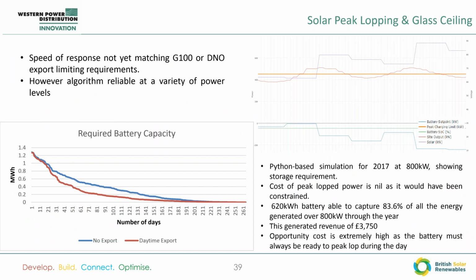So this graph shows how much energy storage would have been needed to peak lop at 80% of the overall power in 2017. Selected 80% because 20% oversizing was deemed to be the smallest oversizing a developer would have the extra expense of looking at a battery rather than just software limiting inverters, because quite a lot of solar parks just have a very high DC to AC ratio and they don't have any batteries to try and take advantage of any of that.